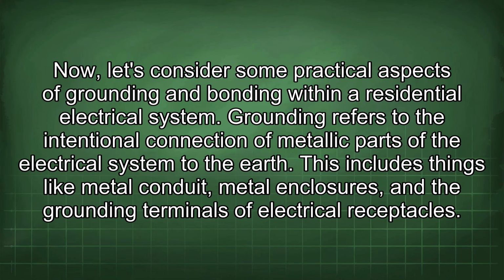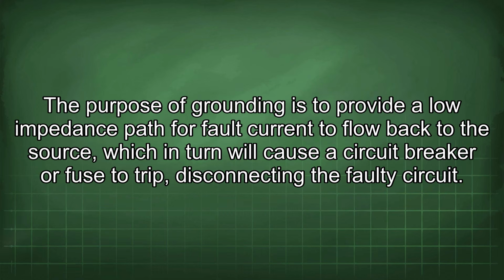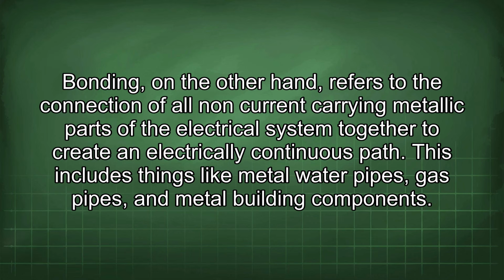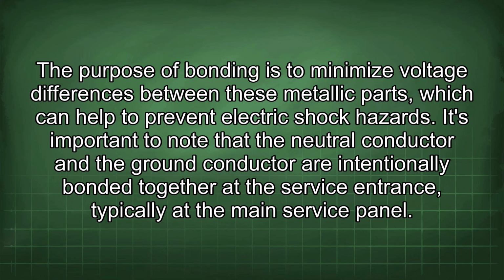Grounding refers to the intentional connection of metallic parts of the electrical system to the earth. This includes things like metal conduit, metal enclosures, and the grounding terminals of electrical receptacles. The purpose of grounding is to provide a low impedance path for fault current to flow back to the source, which in turn will cause a circuit breaker or fuse to trip, disconnecting the faulty circuit. Bonding, on the other hand, refers to the connection of all non-current carrying metallic parts of the electrical system together to create an electrically continuous path. This includes things like metal water pipes, gas pipes, and metal building components. The purpose of bonding is to minimize voltage differences between these metallic parts, which can help to prevent electric shock hazards.